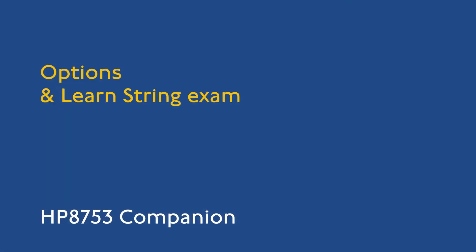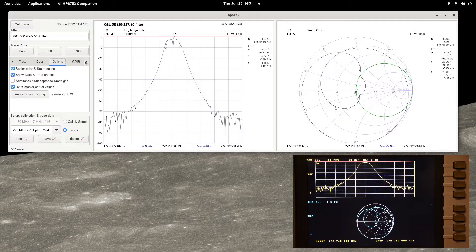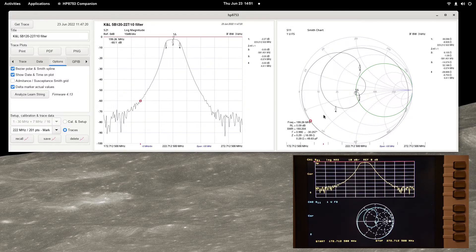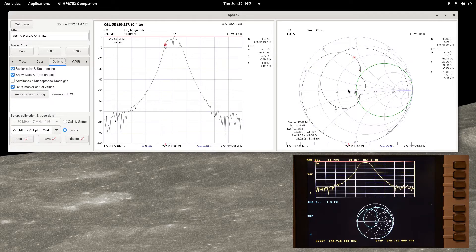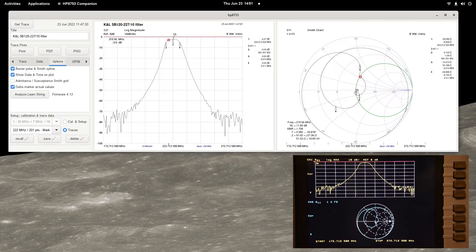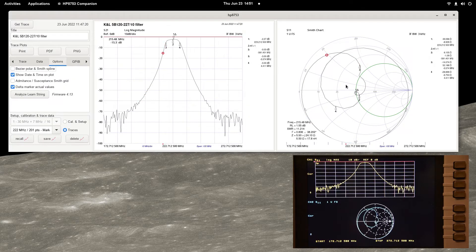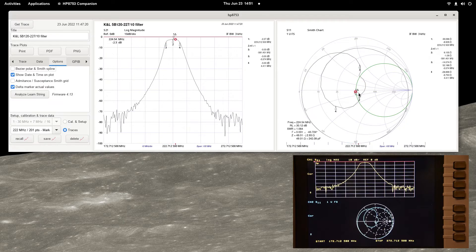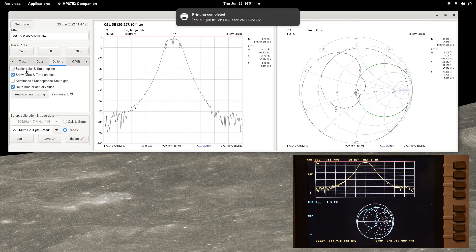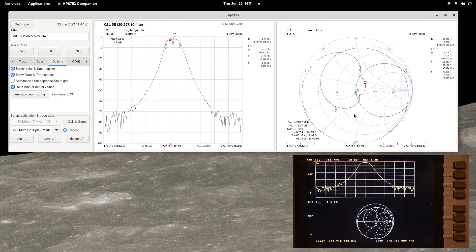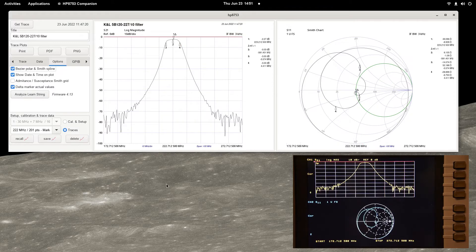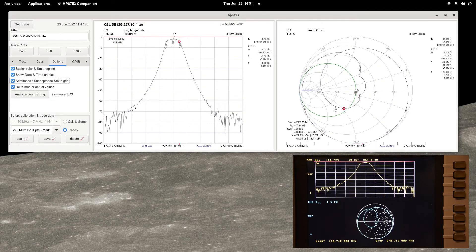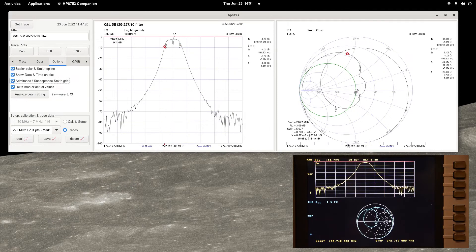Several options are available to change aspects of the displayed plots. Bezier interpolation is used on Smith and Polar plots when the Bezier spline option is checked. Bezier curves fitted between sample points gives a much smoother interpolation than the linear interpolation method used by the HP 8753, which simply joins sample points with lines. Checking the admittance and susceptance Smith grid option changes the Smith grid format and the format of the live marker on Smith chart plots.